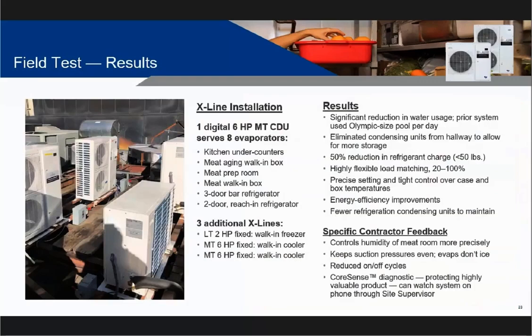Here's a picture of the results. They were able to remove somewhere between 25 to 30 condensing units from that hallway and replaced them with 4 X-lines. He installed one digital 6 horsepower medium temp condensing unit that serves 8 evaporators, covering a variety of applications: kitchen undercounters, a meat aging walk-in box, a meat prep room, a meat walk-in box, a 3-door bar refrigerator, and a 2-door reach-in refrigerator, all medium temp.